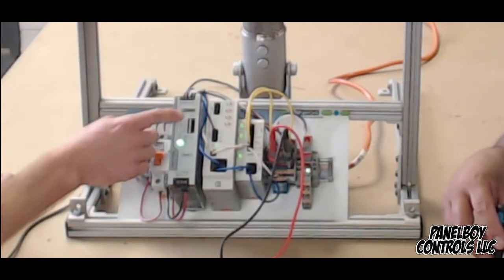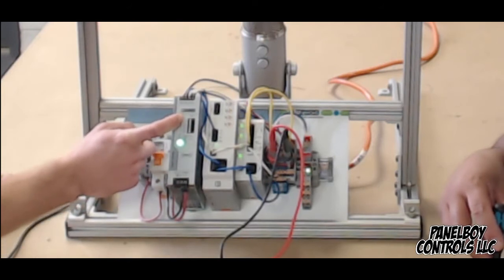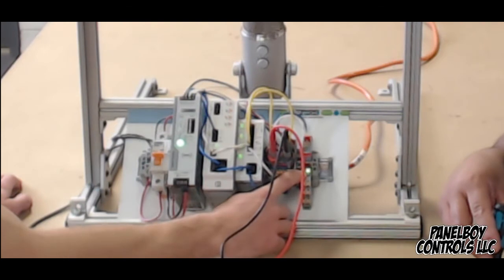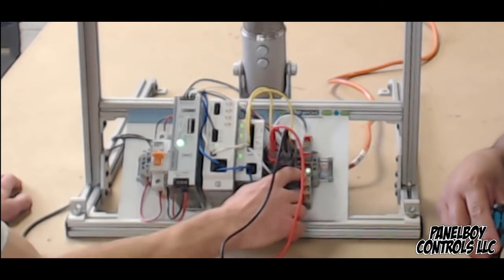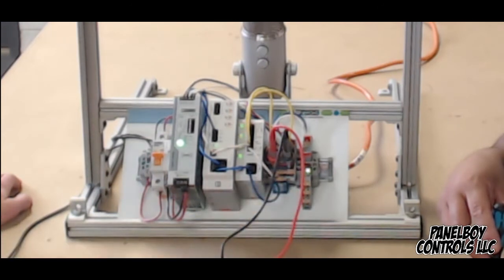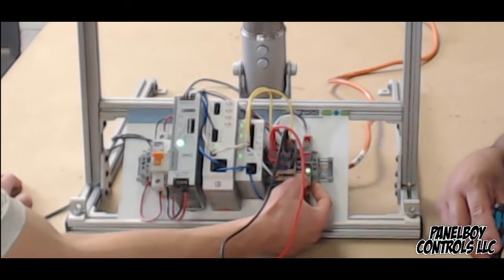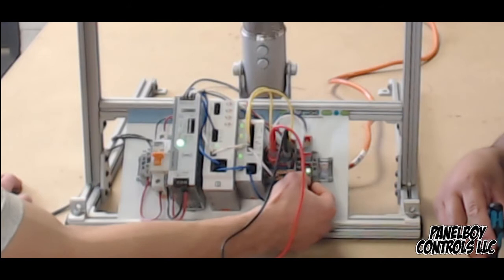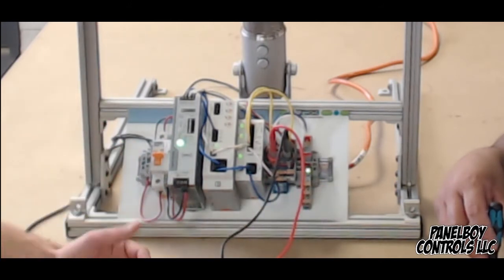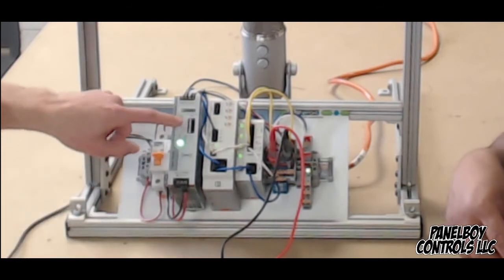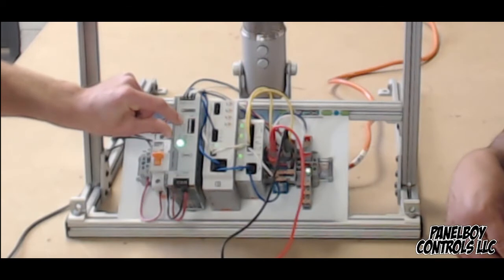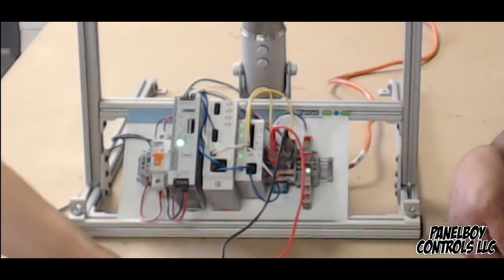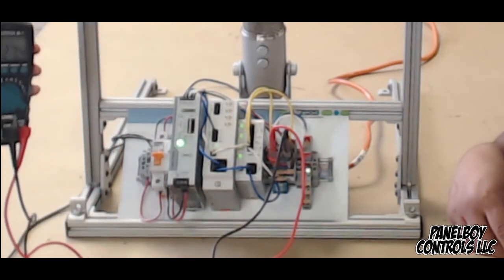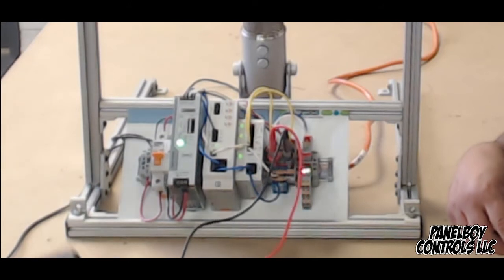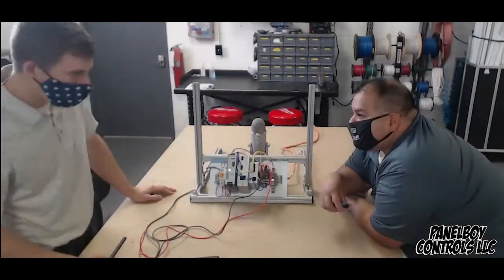We are still set to 24 volts. What I was trying to show is that as I increase the voltage on this, you should see that light go bad or go off. That's because when I try to go above 100 watts, it kicks in and limits it. So setting it to 4 amps, 100 watts would be at 24 volts, just about 4 amps. At 25 volts it'd be 4 amps, so as I go above that you'll start to see an issue probably close to 27 volts. There you go, you see it went bad, it's sitting at 27.5 volts. That's because it's crossing that threshold, whatever the exact NEC class 2 requirement is, and because it's above that 100 watt threshold, it turns off.